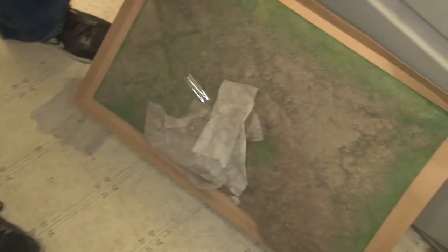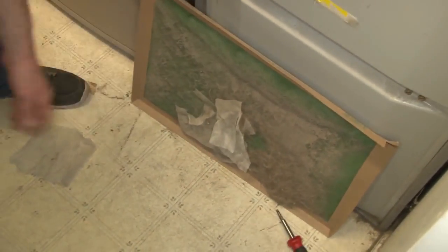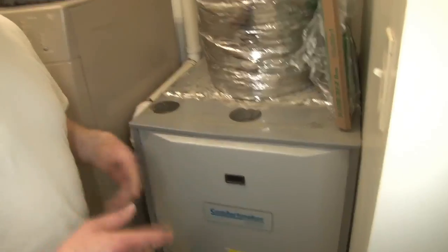And this filter is dirty like this. I mean, this unit's actually still working, but sometimes they get so clogged that there's almost no airflow at all, especially after the winter time, because the heating doesn't require as much airflow as the cooling does. That might be the problem if there's not enough airflow.